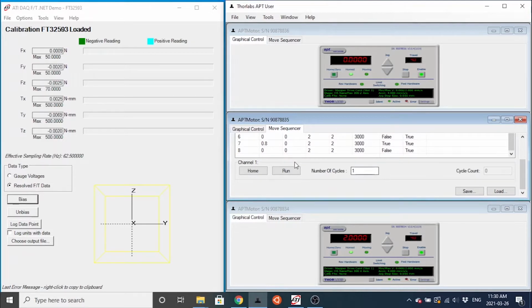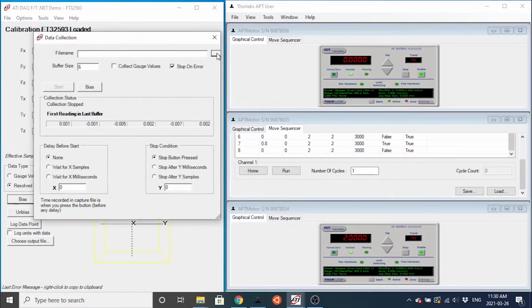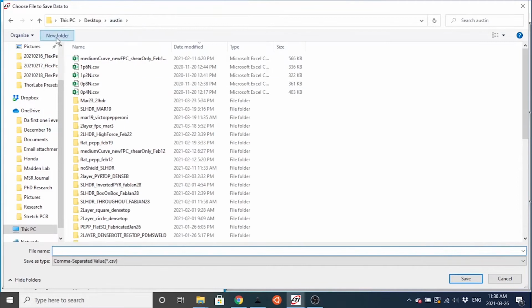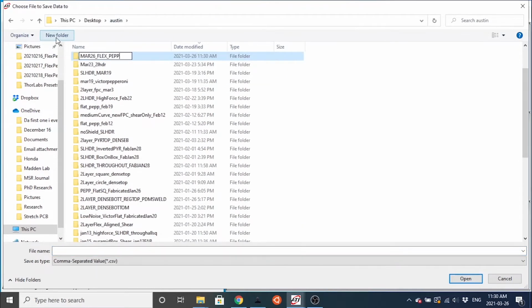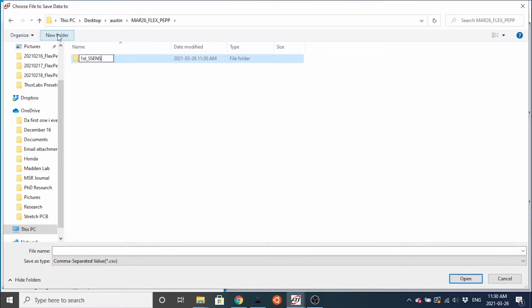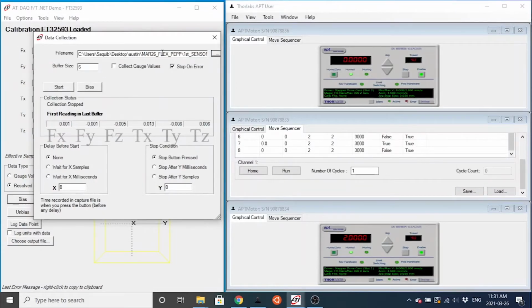We can get ready to capture the load cell data on the ATI software. First click Tools, then Data Collection. Then click the 3 dots to browse for a location to save the CSV file. Ensure you create folders to save the data with meaningful names. For this test, we are shearing the sensor in the X direction with 1.6 newtons of normal force. This is described in the file name. In the data collection screen, the load cell data is described as follows in black text.